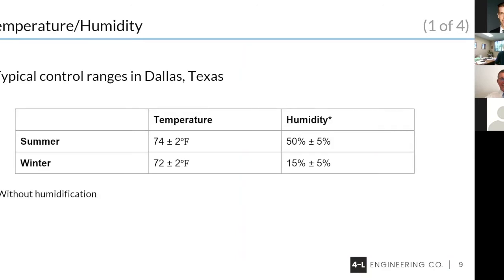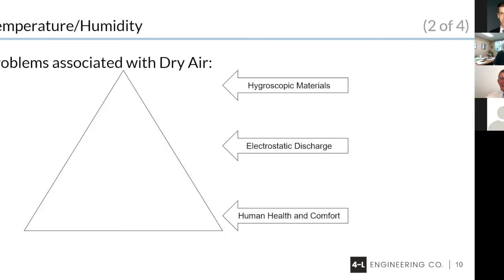When we talk about temperature in a room, typically if we're designing a space, our temperature ranges in the summertime would run 74 degrees plus or minus 2, at about 50% relative humidity in the space. And in the wintertime, we'd get down to around 72 with about 15% relative humidity in this space. And that's without what we call humidification. And this is typically where everybody operates. Next slide. Temperature is the easy thing to control, but humidity is the problem.